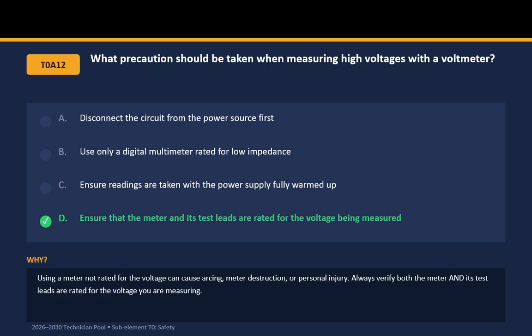What precaution should be taken when measuring high voltages with a voltmeter? D. Ensure that the meter and its test leads are rated for the voltage being measured. Using a meter not rated for the voltage can cause arcing, meter destruction, or personal injury. Always verify both the meter and its test leads are rated for the voltage you are measuring.